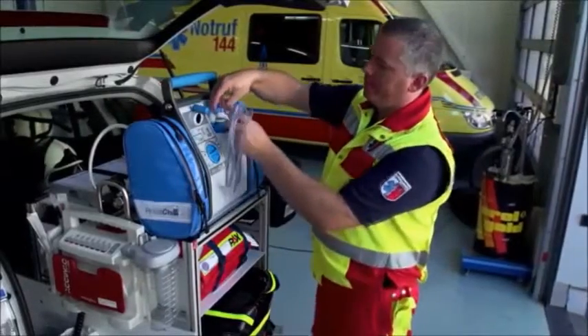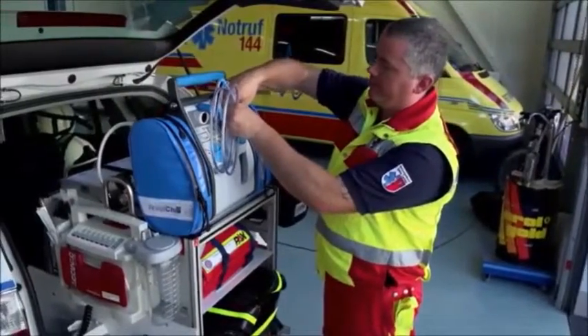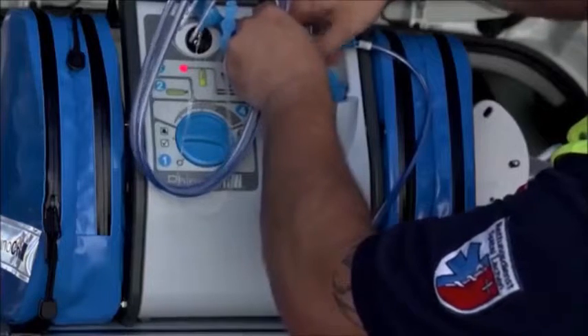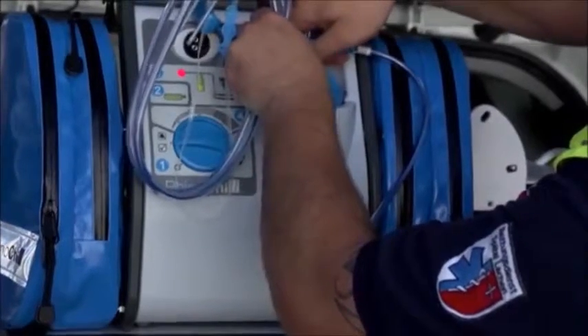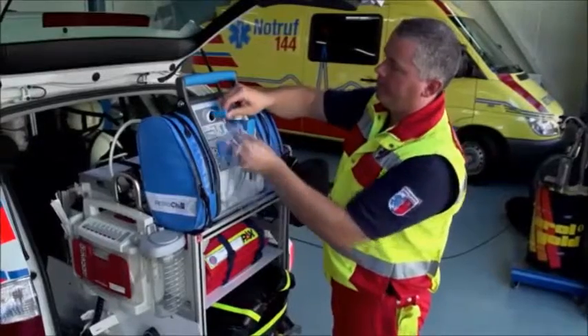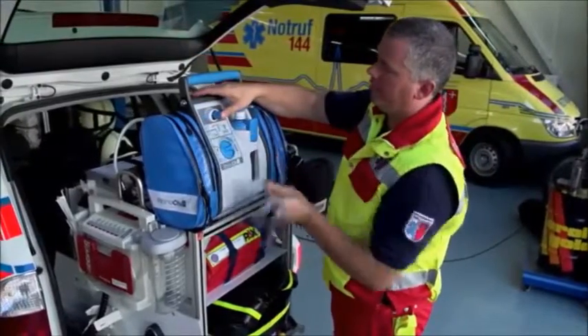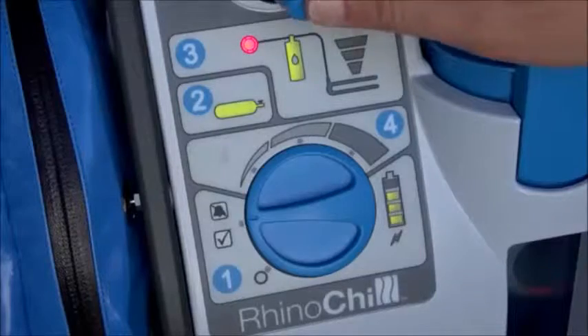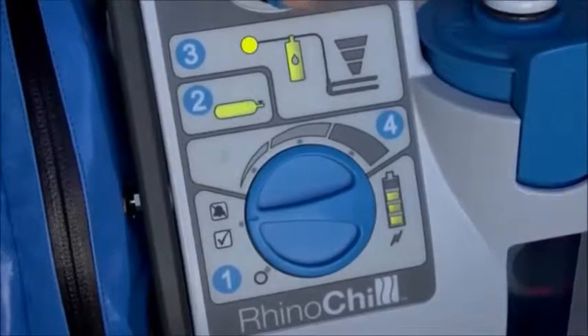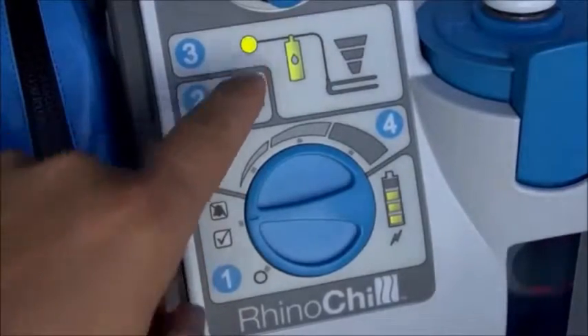Place the catheter bottle interface over the top of the coolant bottle and tighten the catheter bottle cap around the coolant bottle neck. This should be hand tightened only with no tools used to perform this task. Sometimes this can be a little tricky, so if you prefer, you can always do this before the coolant bottle is placed into the control unit. Insert the catheter connector into the control unit catheter connection. The catheter connector light should then illuminate green as the connector clicks into place.